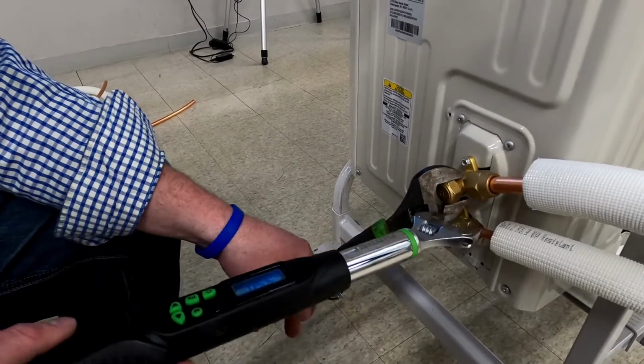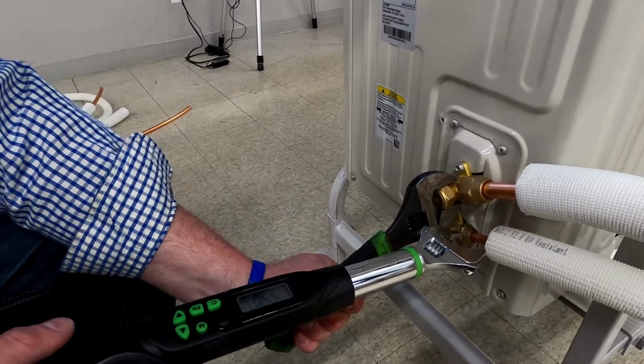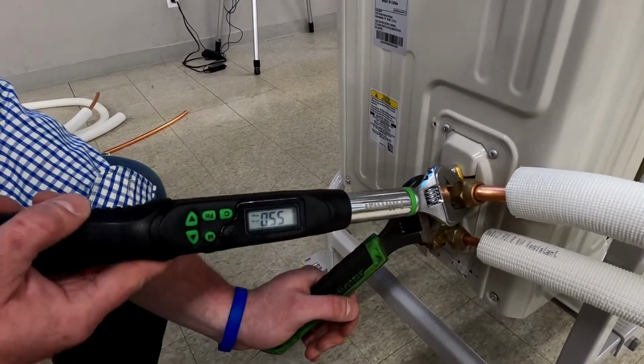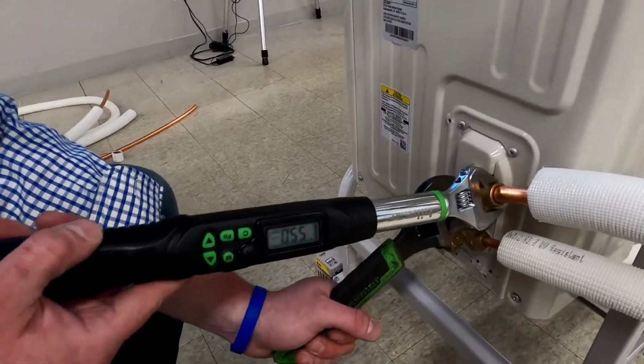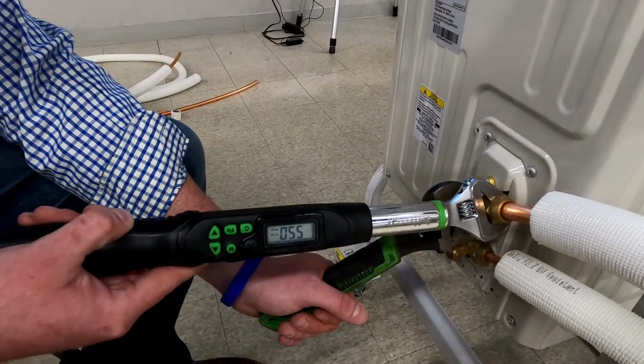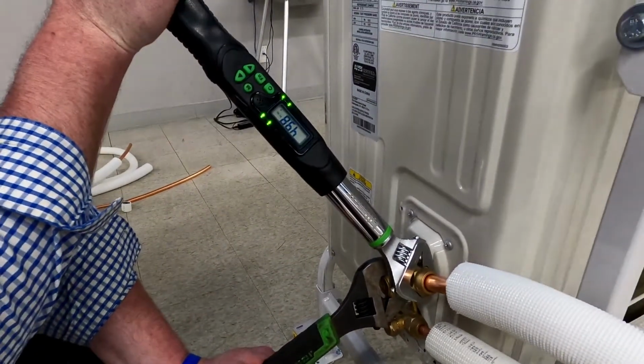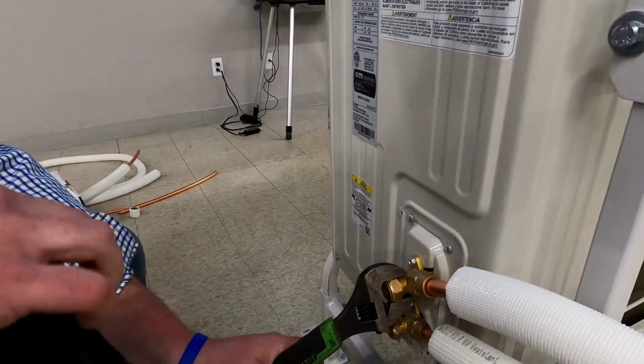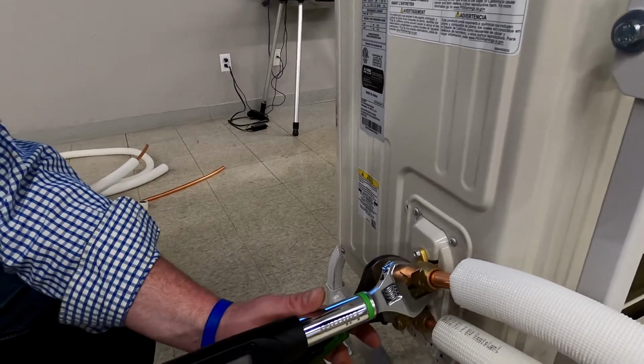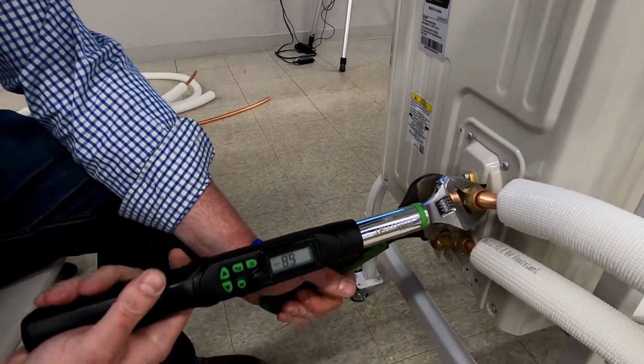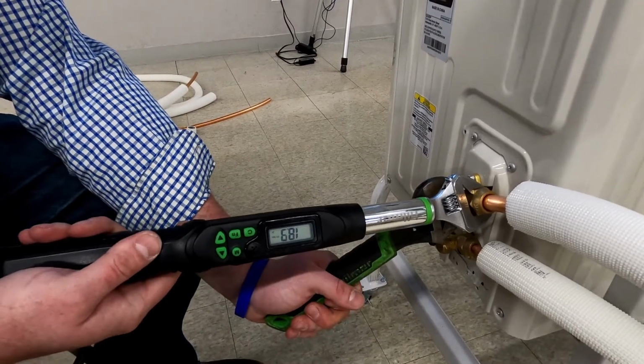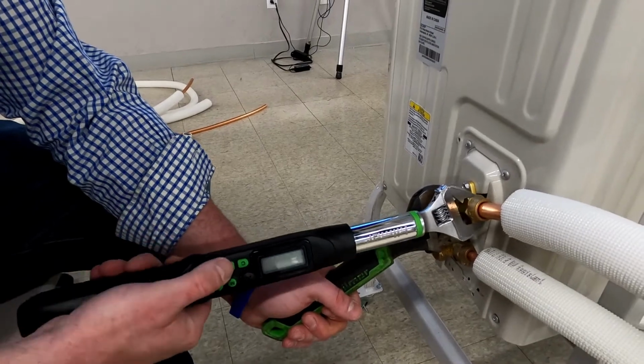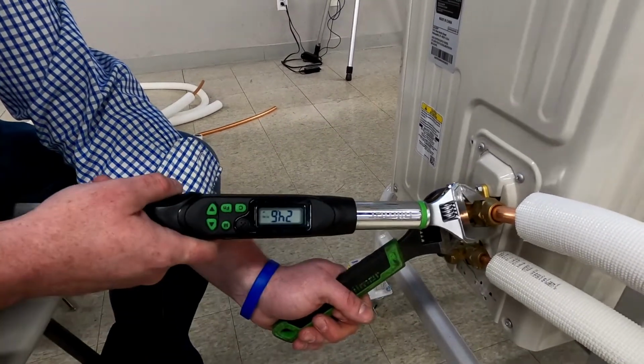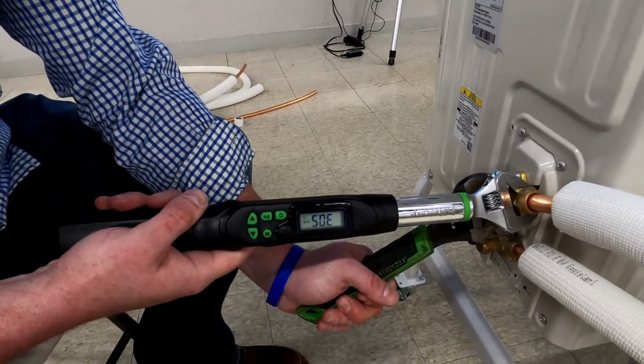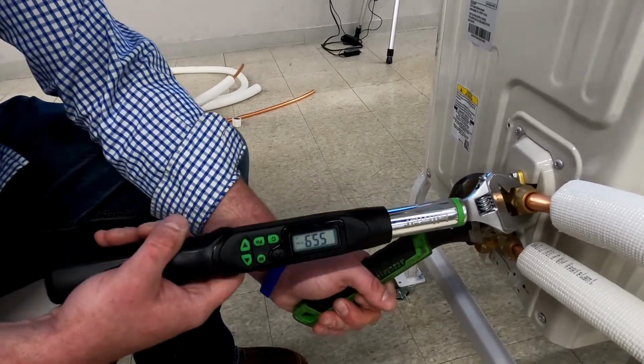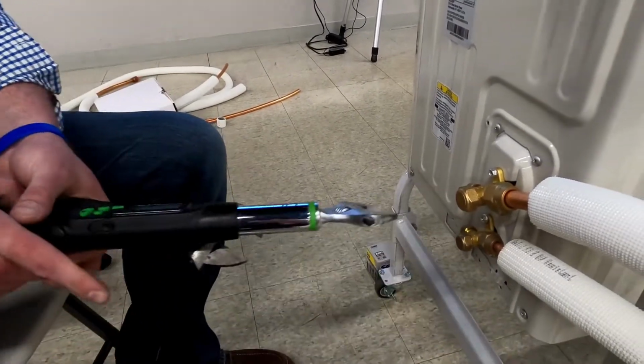One other recommendation is that you use something to back up the service valve because you're putting a lot of pressure on it. Even though it's screwed in, it's still good practice. So you'll see as you start approaching your maximum torque that you have set, the wrench will start alerting you and the lights will actually increase until you reach the red. So now we have that properly torqued.